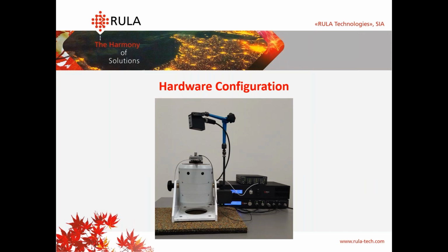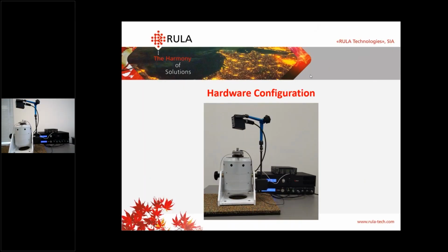Here you see on this side our today's hardware configuration. Let me turn on the camera. In today's test, we are running our sine. We have an RLC21 controller, a relay 200 amplifier, and our strain gauge amplifier RLS39. Here we have our regular TV51-110 shaker. We have a beam on it, and we have 3 sensors here. On the beam, we placed a strain gauge sensor and connected it with our strain gauge amplifier. On the top, we have a 10 millivolts per G accelerometer, and here on the right side, you see we have a laser vibrometer. And now I think we can go to our software.